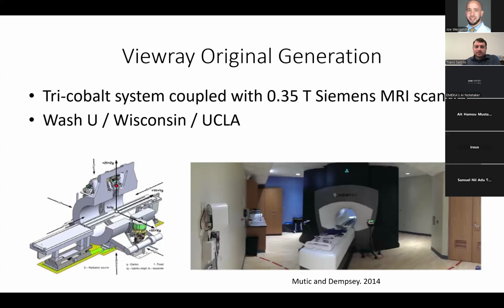Another reason that this is attractive, and we'll talk about this a bit later, is because the low magnetic field is sufficient to give you decent image quality to still visualize the soft tissue contrast that you want, but it influences the radiation a lot less than some of your higher field systems like the Elekta Unity, which implements a 1.5 Tesla scanner. These tri-cobalt systems were first introduced at WashU, as I mentioned earlier, but also at Wisconsin and at UCLA.